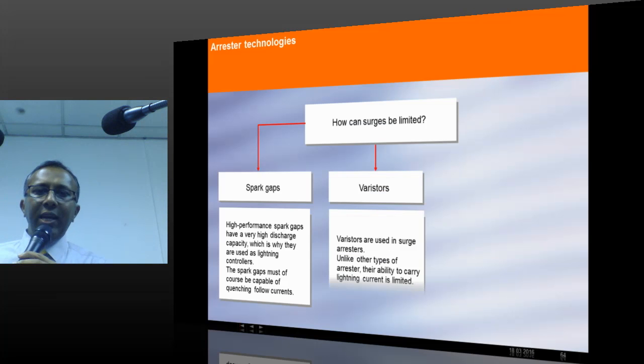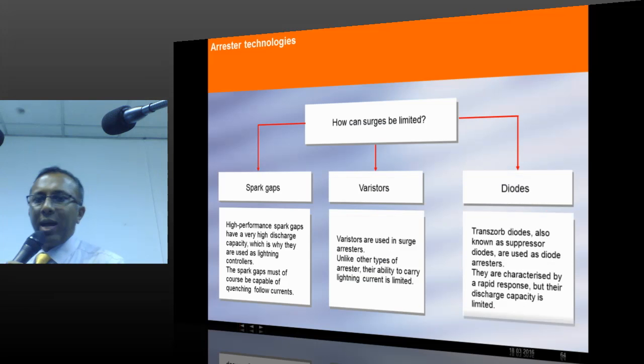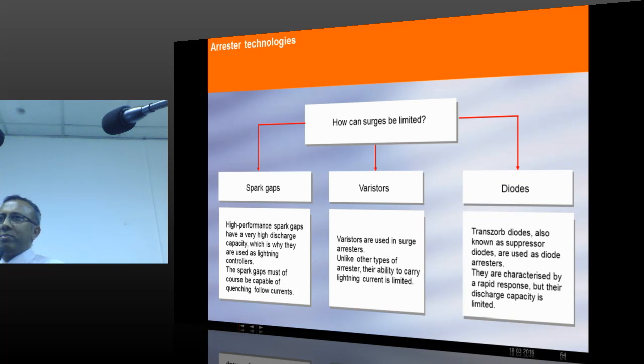And what kind of SPDs are there? Spark gap, varistor, diode. So spark gaps are very strong devices but a little bit slow. Varistors are faster than spark gaps but the energy handling capacity is limited. Diodes are very fast but can handle only a little energy. So the spark gap can handle lightning current, very large current. A varistor can handle small surge currents.